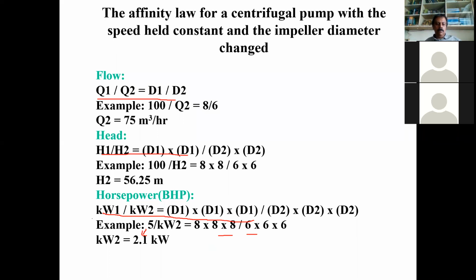So a huge potential for saving is there when you identify a bigger pump and you change the impeller. An impeller change should be adopted when you know for sure that a fixed, reduced rate of flow of water is required, and that is not going to vary with time. Then you go in for an impeller change.